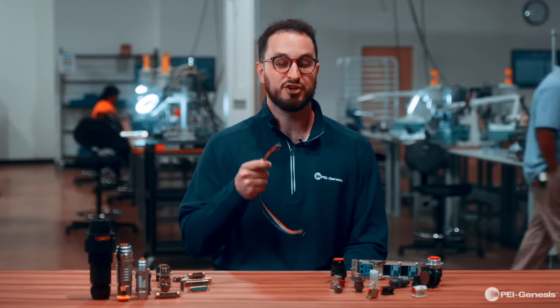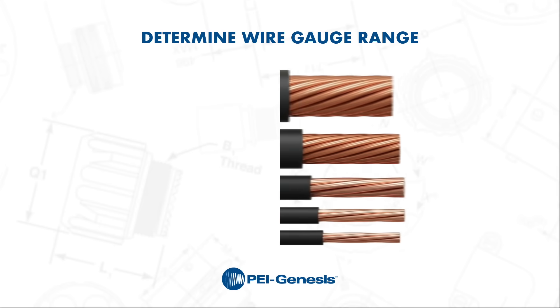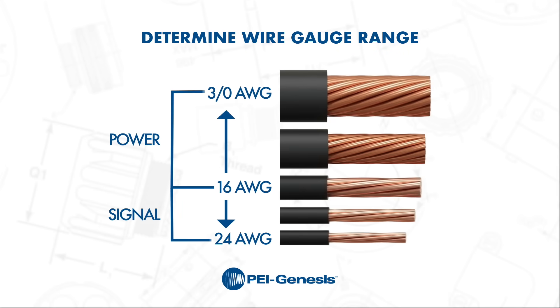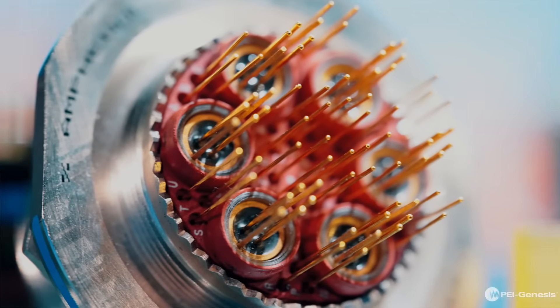First, we need to determine wire gauge range. The wire gauge will relate to the size of the contacts, and the size of the contacts will help us determine which connector series we can use for your application. Typically a contact 16 AWG or larger is associated with transmitting power, while a contact smaller than 16 AWG is associated with transmitting signal. Knowing your wire gauge or contact size ensures that your connector can handle the electrical load without failure or overheating.